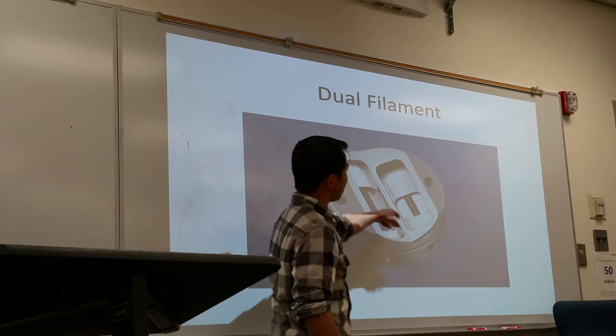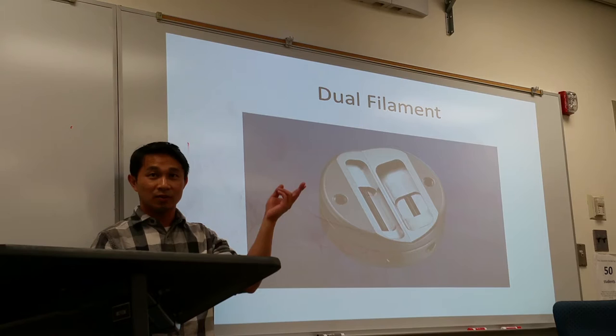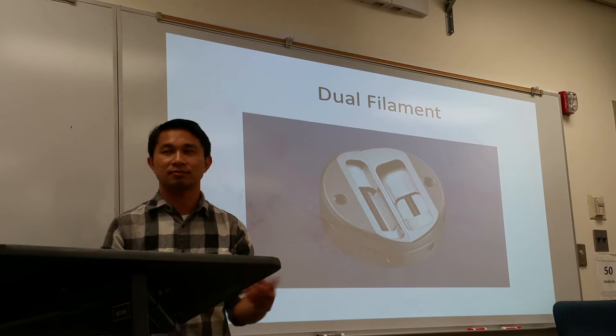Here is an image of a dual filament — one large and one small. When we select 400 mA, for example, the focus selector will automatically switch between large and small filament.